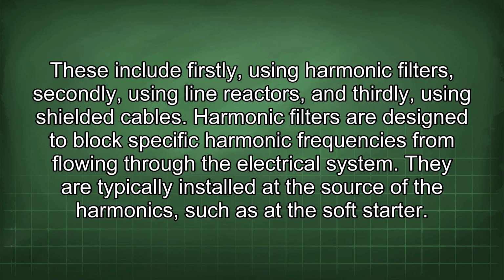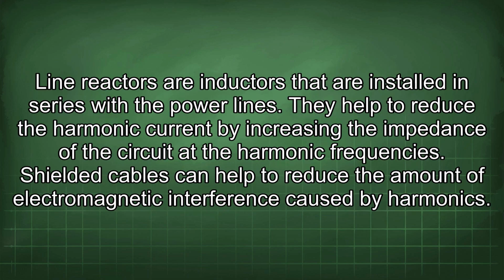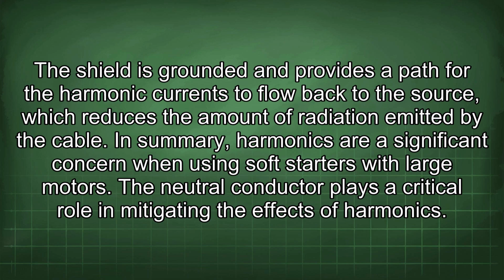Harmonic filters are designed to block specific harmonic frequencies from flowing through the electrical system. They are typically installed at the source of the harmonics, such as at the soft starter. Line reactors are inductors that are installed in series with the power lines. They help to reduce the harmonic current by increasing the impedance of the circuit at the harmonic frequencies. Shielded cables can help to reduce the amount of electromagnetic interference caused by harmonics. The shield is grounded and provides a path for the harmonic currents to flow back to the source, which reduces the amount of radiation emitted by the cable.